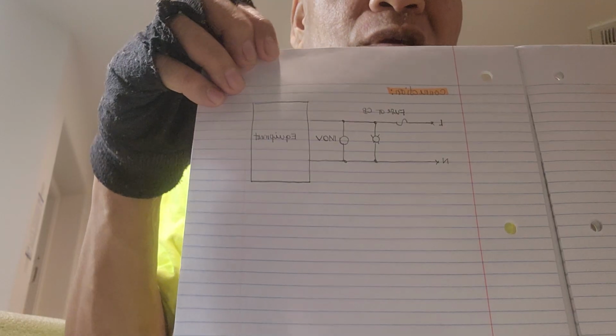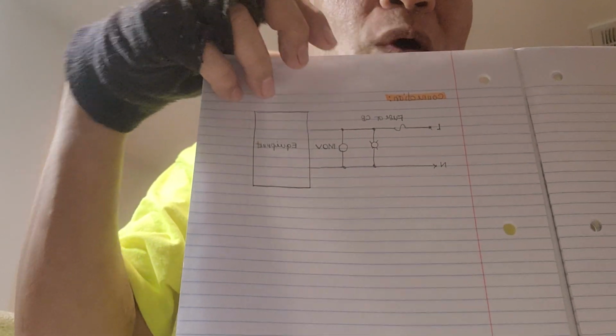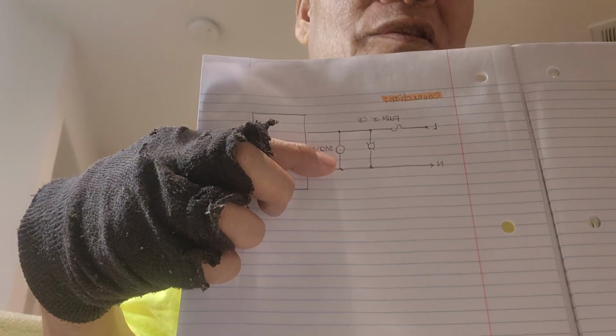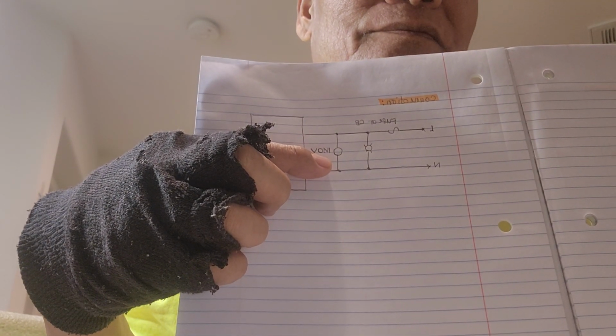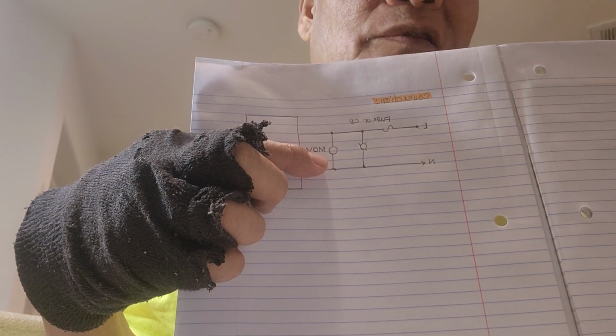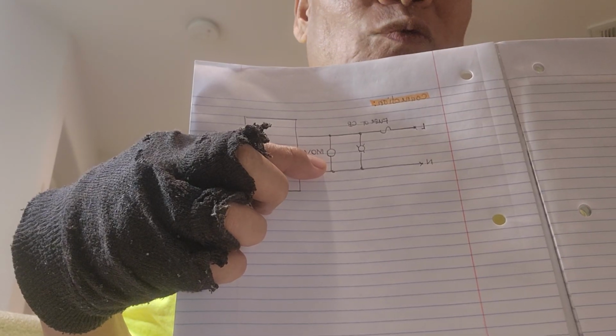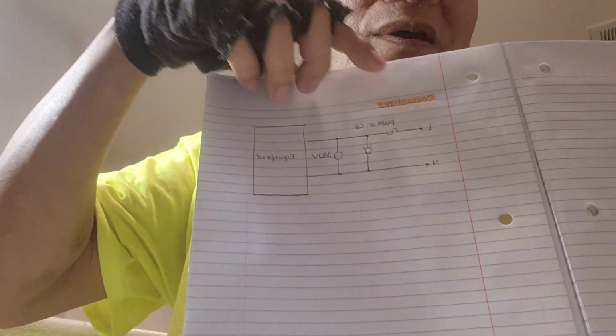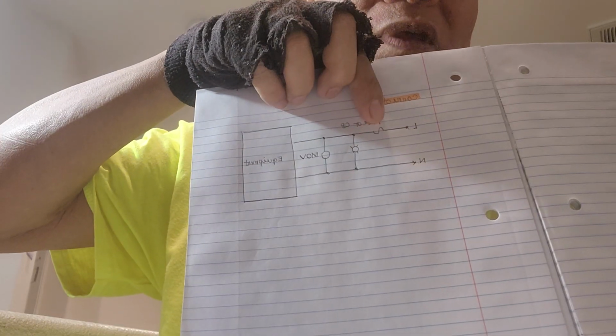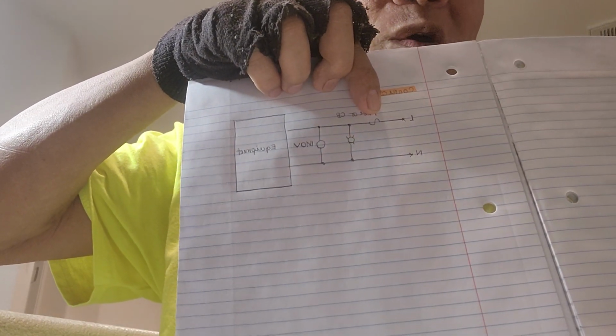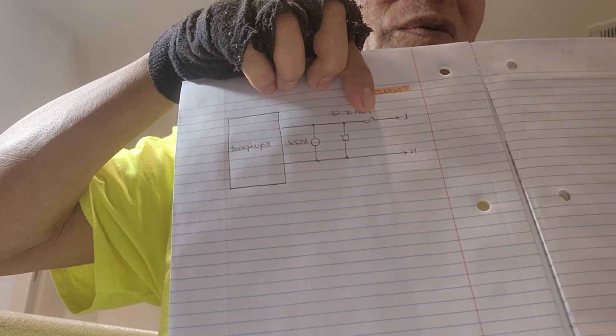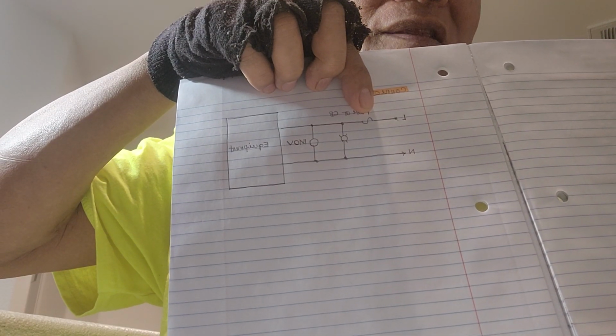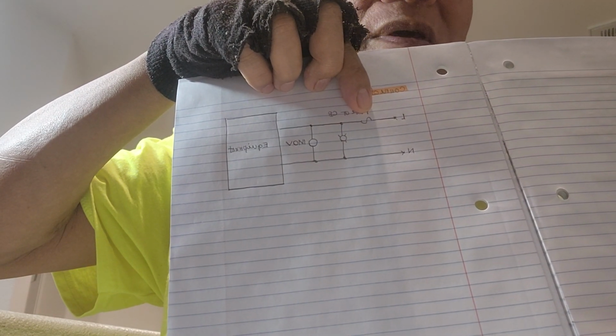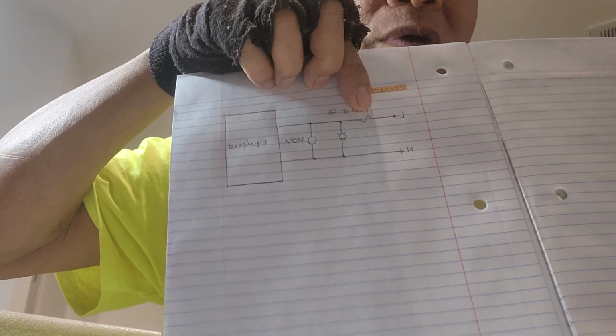Because if there is a voltage surge, the one that will absorb the overvoltage is this metal oxide varistor. It will try to short out itself. By shorting itself, it kills the voltage supply going to the equipment, and the fuse or circuit breaker is supposed to blow. So when the fuse or circuit breaker is blown, meaning there's a short circuit, the next thing we check is the metal oxide varistor.